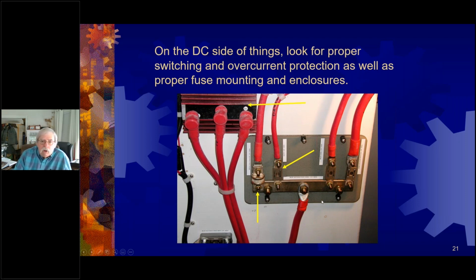And there's no covering over any of these fuses. And they're high amp fuses. So that tells me there's quite a bit of current involved. It's also pretty heavy gauge cable. The other aspect of this particular installation that's troublesome, although it was a diesel fueled boat, if it were a gasoline fueled boat, some fuses require that they be installed in a prescribed fuse holder with a protective cover to achieve their ignition protection rating. And well, that was totally ignored in this case.